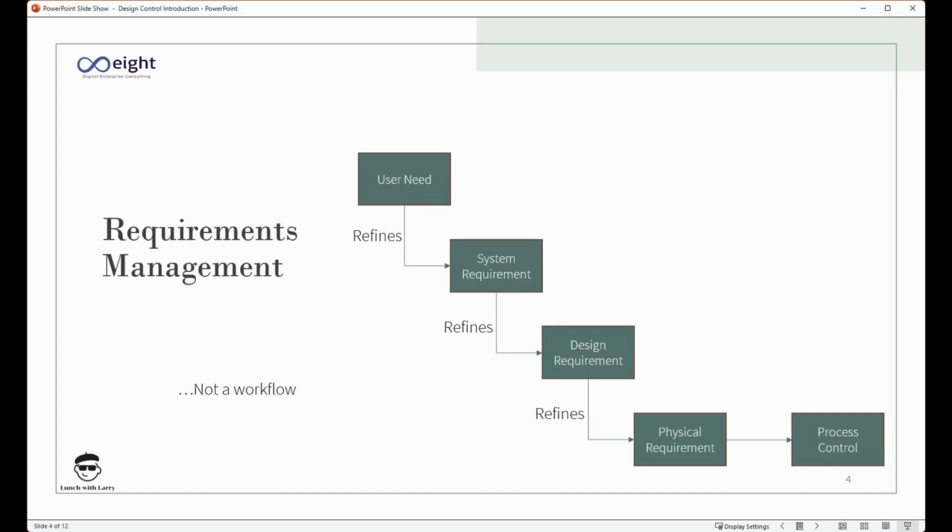In med device, as a matter of fact, when I talk to people at the FDA, one of their biggest complaints about submissions is they really don't understand from the submission what the device does. What we're attempting to do here is to provide this formal deconstruction so that it becomes very clear to them what the device does and how we define what good performance is.